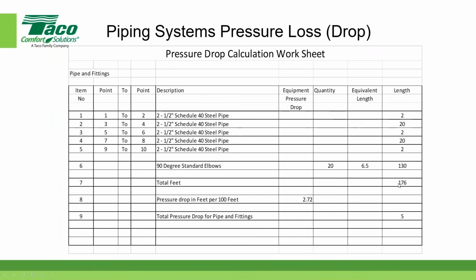So if I multiply 176, now remember, this is the pressure drop in feet per 100 feet. So I have 176 feet. If I divide that by 100, then I'd have 1.76 times 2.72, which is approximately equal to 5. Any questions about how I generated this pipe and fittings table and how I calculated the pressure drop based on the equivalent length?